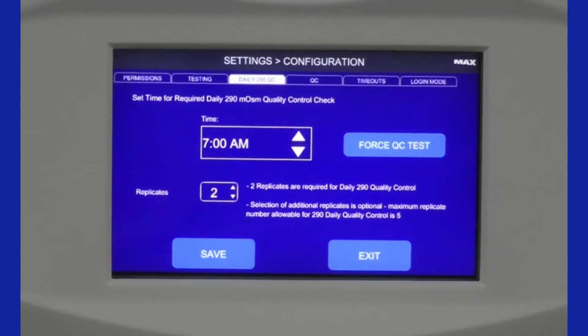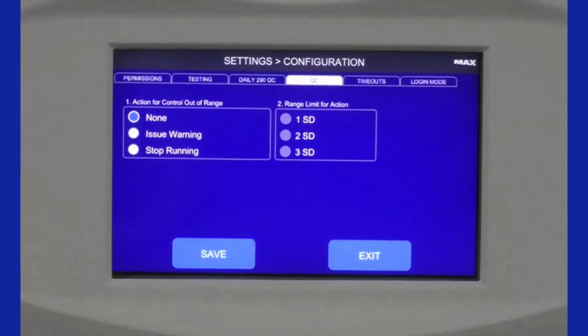But just know that the instrument will prevent you from performing any patient testing until this daily Clinitrol 290 check has been performed. Let's say you're somewhere within that 24-hour time frame and you feel like there's a need to force that check and you want to run that Clinitrol 290 check against your baseline earlier than you typically would at that 24-hour time frame. You can go into this menu and just hit the Force QC Test button, and it will do just that. It will run your 290 and check it against that baseline you established at the time of calibration.